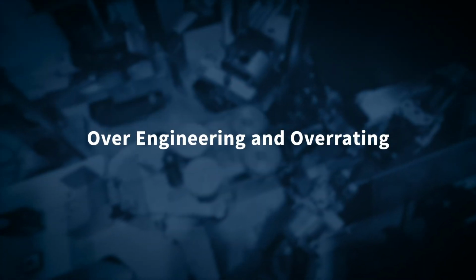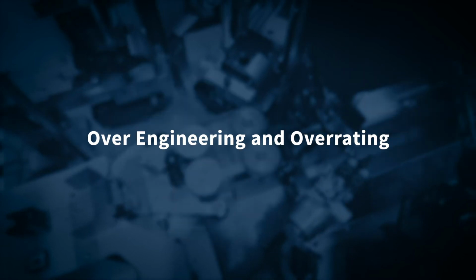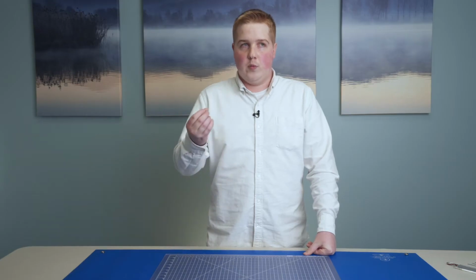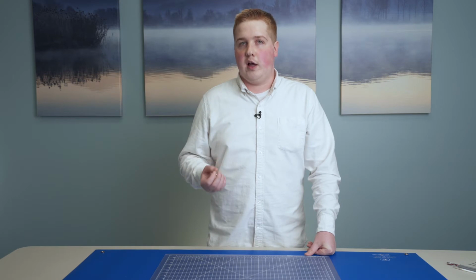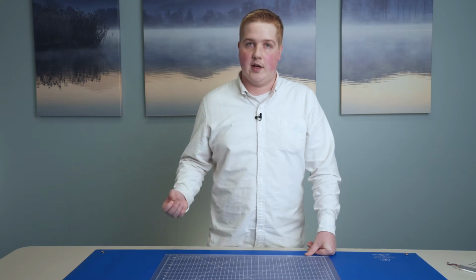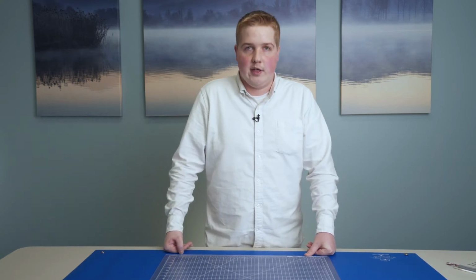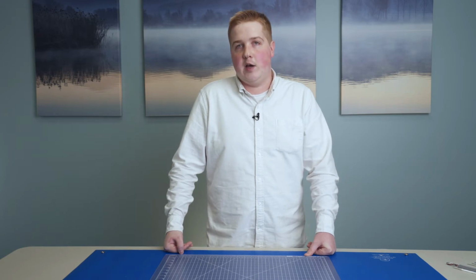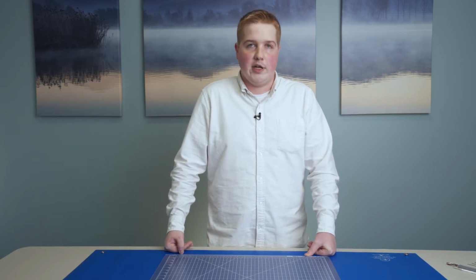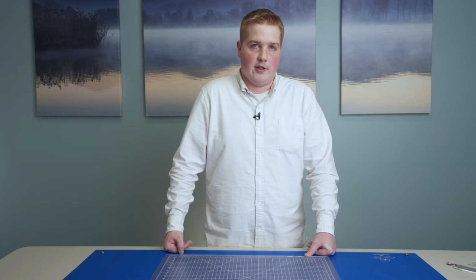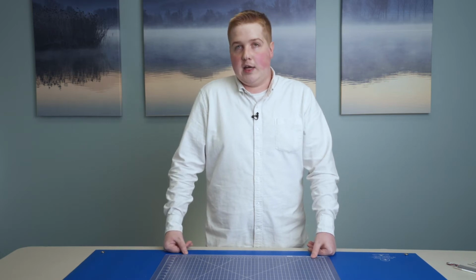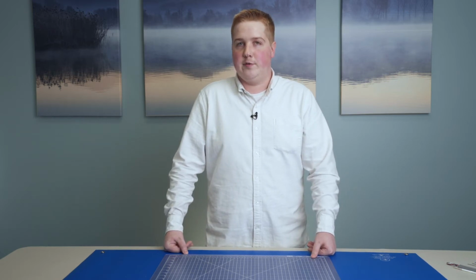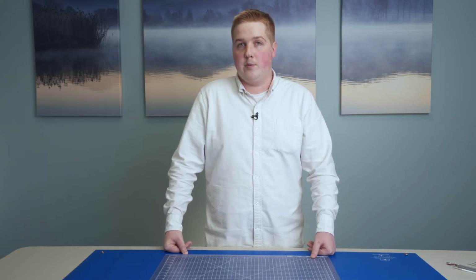Another really common design error that can arise is over-engineering and aspects that are not utilized properly or fully in a design. There are times when we will see a specified cable that comes with a foil and a braid shielding on it, but it is not connected to ground. Unfortunately, a shielding is not going to be effective if it's not connected to a ground somewhere on the assembly.